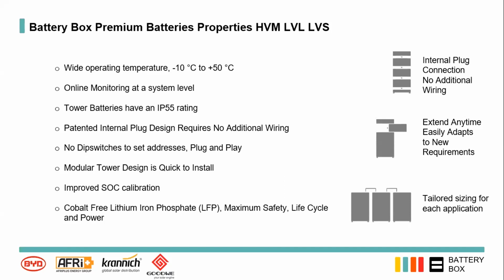Because it's a tower design, we've introduced a new patented plug design that needs no additional wiring between your modules. Where previously you had to put cables in between your modules, which were points of failure, and there was a lot of wiring required, now you just put your modules on top of each other, and there are no extra dip switches to set, etc. So it's all very much plug and play. The modular tower design is very quick to install. Sometimes taking the battery modules out of their packets takes longer than actually putting your battery in a tower.